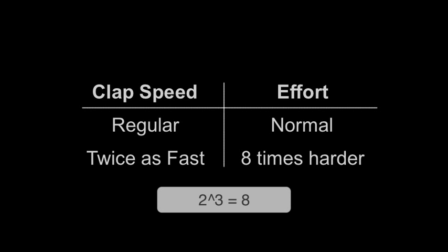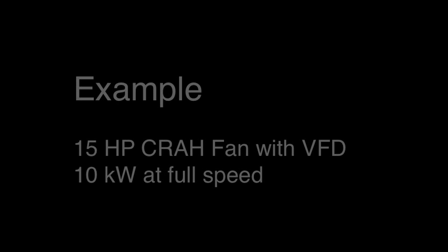Now let's look at a specific example for a data center. Let's say we had a CRAH unit with a 15 horsepower fan motor that we retrofitted with a VFD. Typically, at full speed, that fan would draw about 10 kW. But now with a VFD we have the ability to reduce the fan speed.